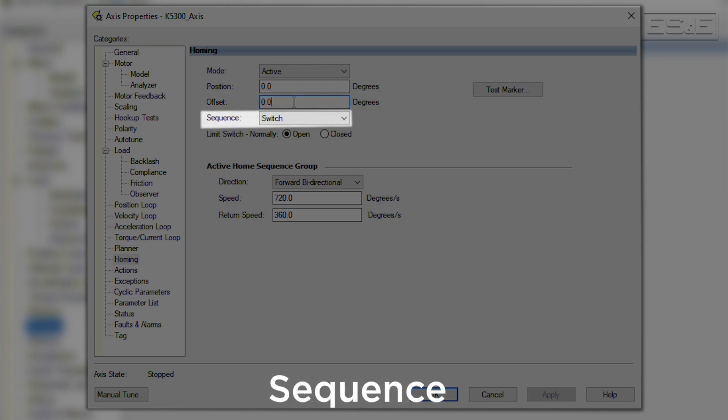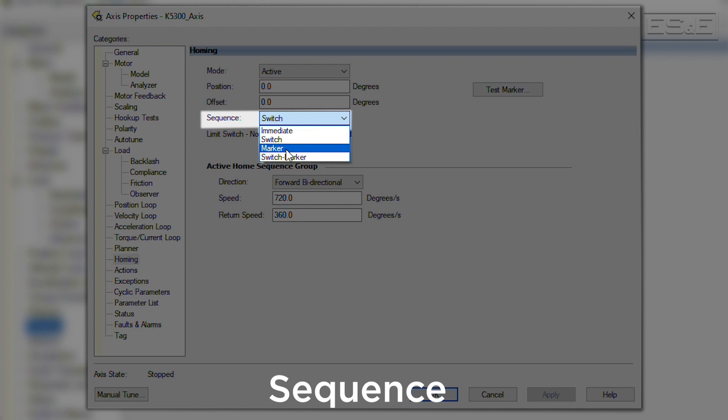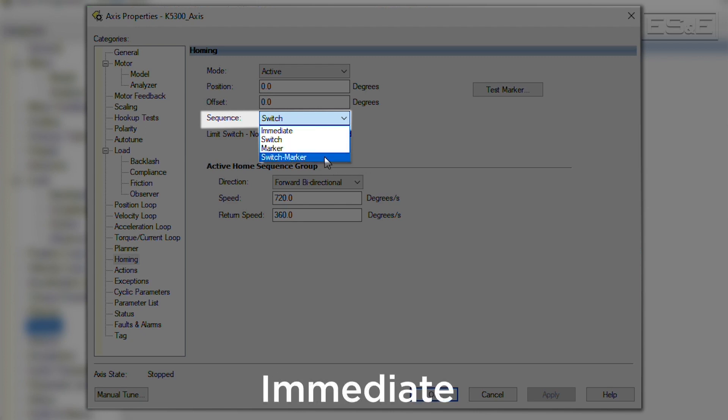Then there is the sequence selection. There are four options: immediate, switch, marker, and switch dash marker. If immediate is selected, then the actual position of the axis will be set to the value set in the position field immediately upon executing the MAH.